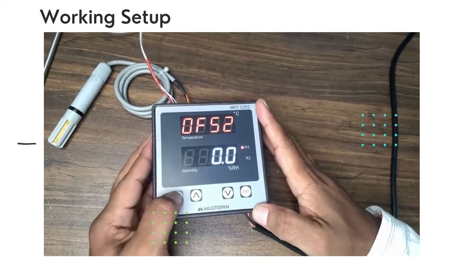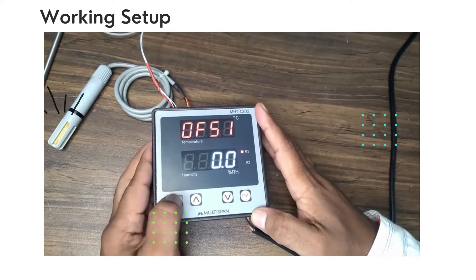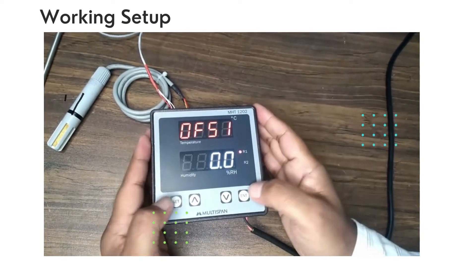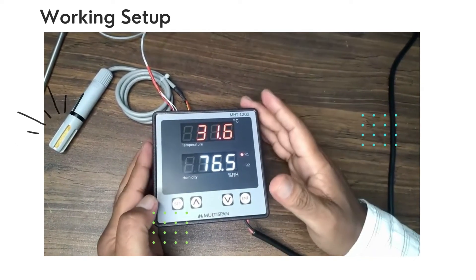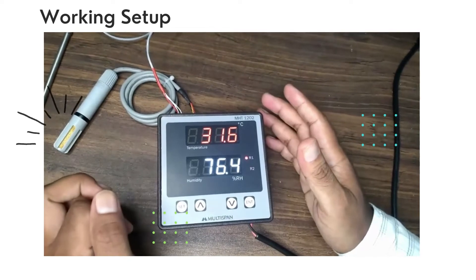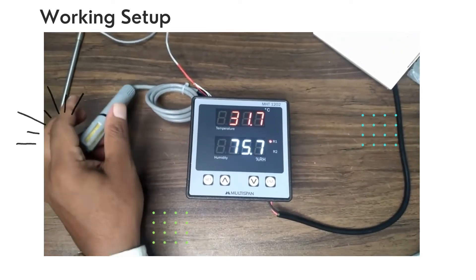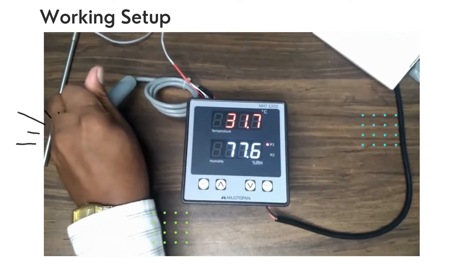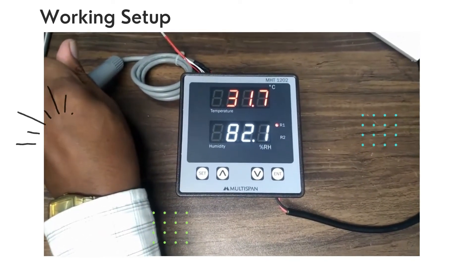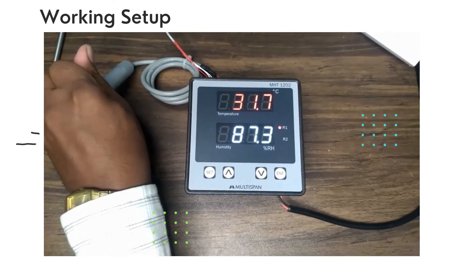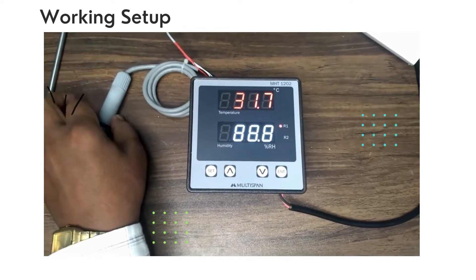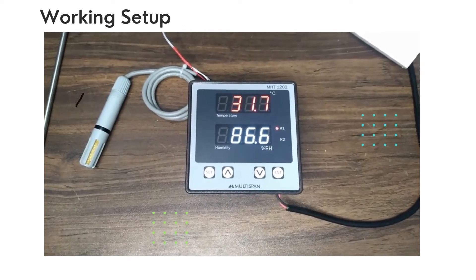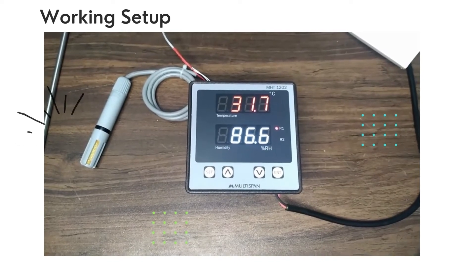Now press Enter key to exit from the menu. Now if you want to check if our humidity sensor is working or not, just put your hand on the bottom of the humidity sensor. It will detect your hand's humidity and here you can see humidity will increase accordingly. And if you put down the sensor, humidity will reduce.